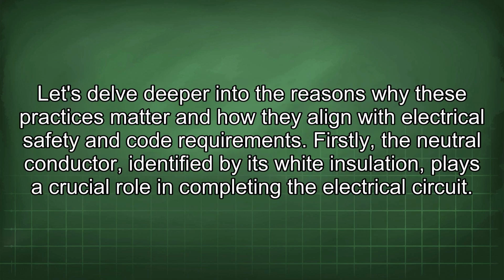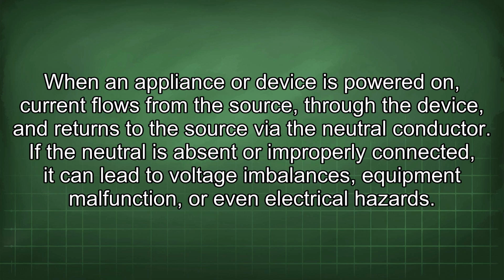Let's delve deeper into the reasons why these practices matter and how they align with electrical safety and code requirements. Firstly, the neutral conductor, identified by its white insulation, plays a crucial role in completing the electrical circuit. When an appliance or device is powered on, current flows from the source through the device and returns to the source via the neutral conductor. If the neutral is absent or improperly connected, it can lead to voltage imbalances, equipment malfunction, or even electrical hazards.